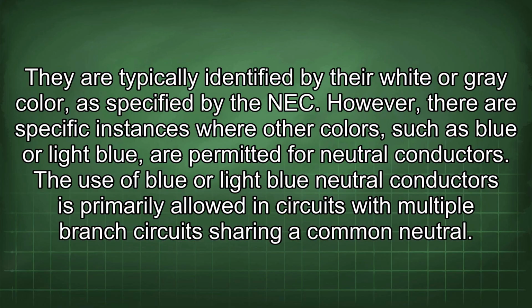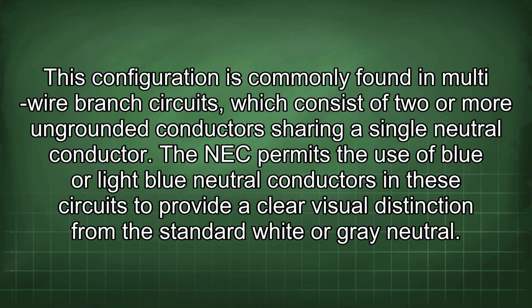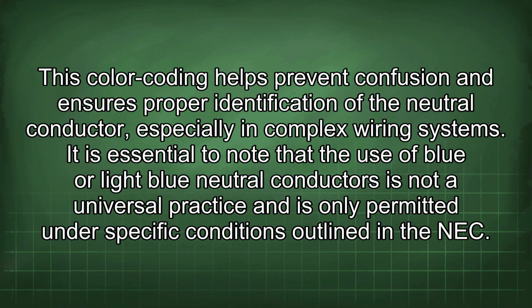The use of blue or light blue neutral conductors is primarily allowed in circuits with multiple branch circuits sharing a common neutral. This configuration is commonly found in multi-wire branch circuits, which consist of 2 or more ungrounded conductors sharing a single neutral conductor. The NEC permits the use of blue or light blue neutral conductors in these circuits to provide a clear visual distinction from the standard white or gray neutral. This color coding helps prevent confusion and ensures proper identification of the neutral conductor, especially in complex wiring systems.